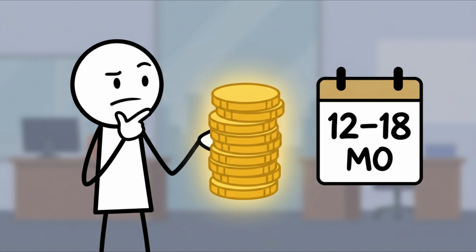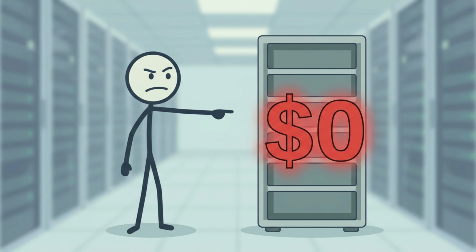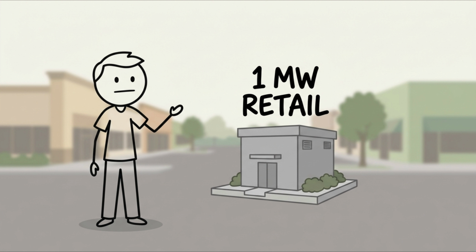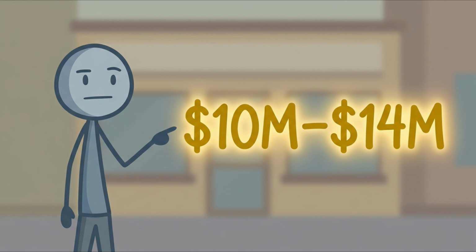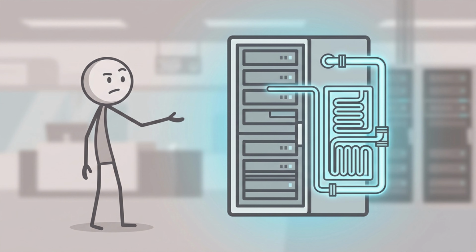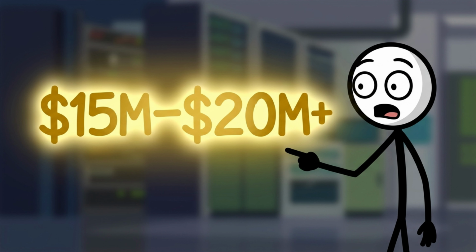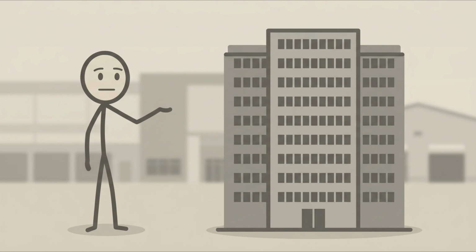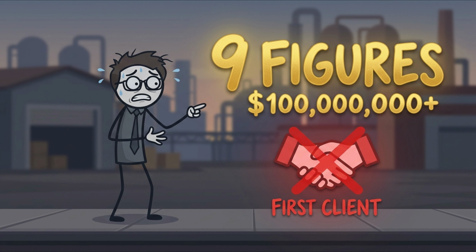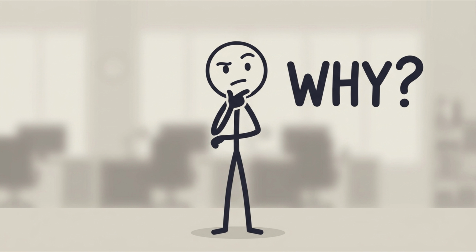Add working capital to cover 12 to 18 months of operating expenses before you hit meaningful occupancy, because empty racks generate zero revenue and full overhead. All in, a modest 1 megawatt retail colocation facility built into an existing building runs $10 million to $14 million. Push into AI-optimized territory with liquid cooling and higher power density, and Terrapin puts that same megawatt at $15 million to $20 million plus. Scale to a real multi-tenant facility, and you're in 9 figures before you've signed your first client. So the question becomes obvious.